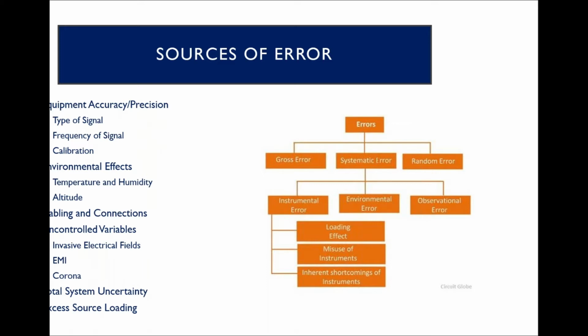In addition, you have your cabling connections. Your high voltage signals may act differently depending on how your cables are routed or what cables are being used, the quality of your terminations, for example. There are a lot of uncontrolled variables as well. You may have some invasive electrical fields that will either cause error in your sensitive measurement electronics or even on your high voltage signal. Things like EMI will come into play and also cause that kind of effect. A big one with high voltage would be corona, which would be generated from your high voltage sources. And we'll talk a lot more about corona a little later in this presentation.